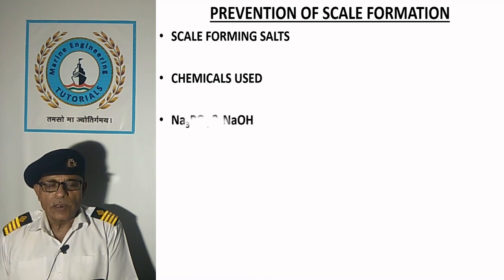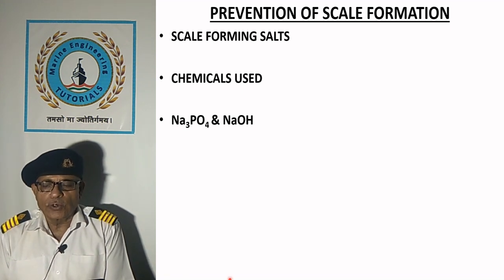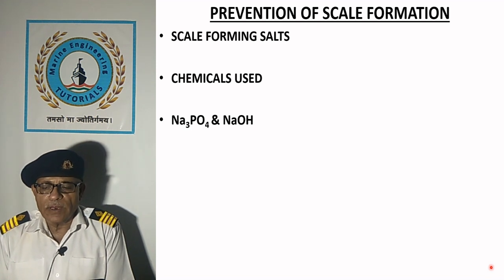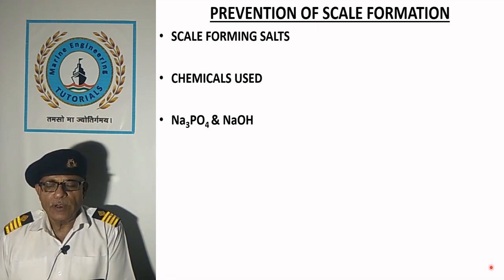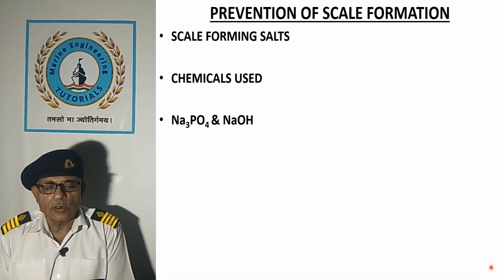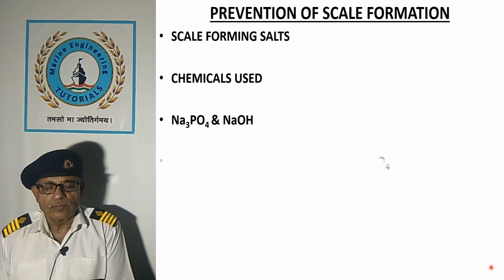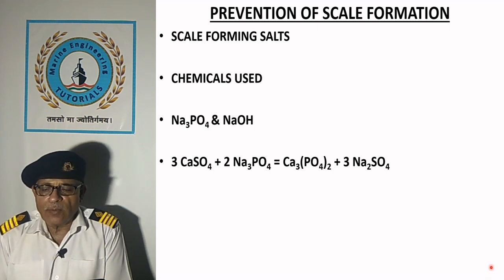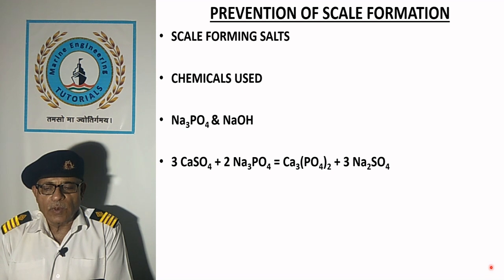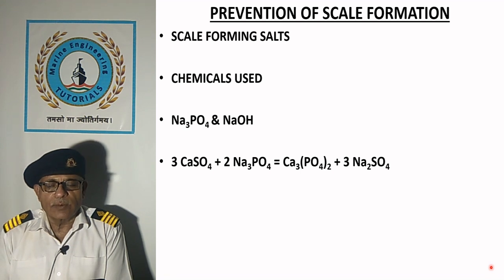Trisodium phosphate is used and helps in precipitating scale-forming salts into sludge. It also provides alkalinity. Any shortfall of alkalinity is made up by use of caustic soda. Phosphate reacts with the scale-forming salts, and sodium sulfate formed in the reaction is highly soluble in water, whereas calcium phosphate is precipitated which can be removed by blowdown.